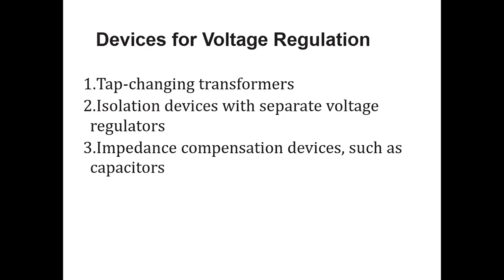So this is a good method, the tap changing transformers. Either you go for off load, otherwise you go for on load. On load means automatically you will get the tap changing. But if you think about the off load, then we have to stop the whole system, then make the change, so that is a manual system. That is time consuming. So that's why, instead of the off load tap changer, we have to go for the on load tap changer.